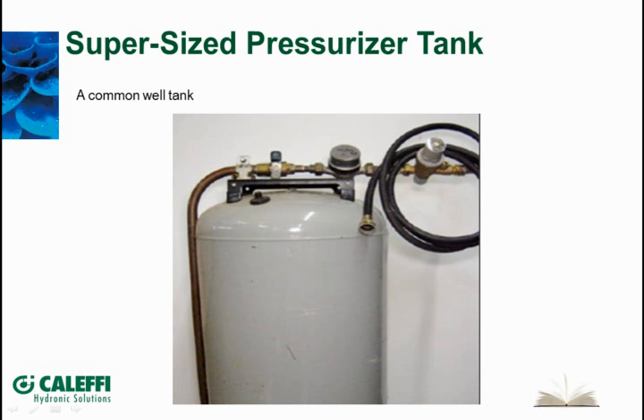So when you come back the next time, you've got enough glycol with you to do that. It's also a nice leak finder. If you've got a radiant job where you suspect you might have a leak in one of your loops or one of your in-slab zones, you can just put this on the job and leave it for a couple days, a week, or a month, and go back and you can see how much fluid has leaked out of your system, so you can help see how big of a leak you've got and what you're going to do about it.